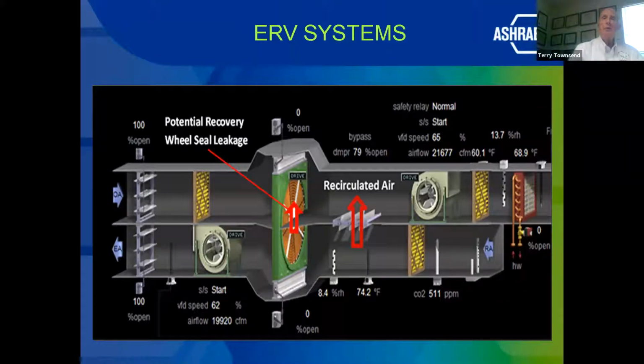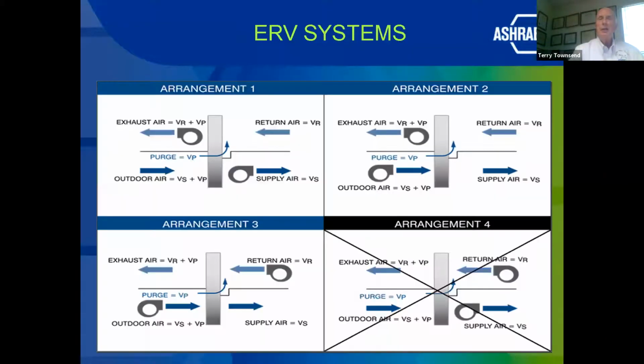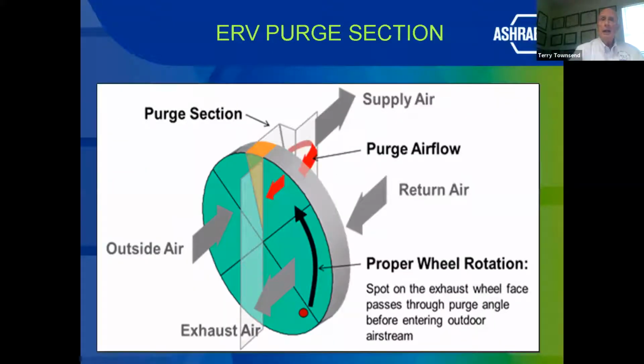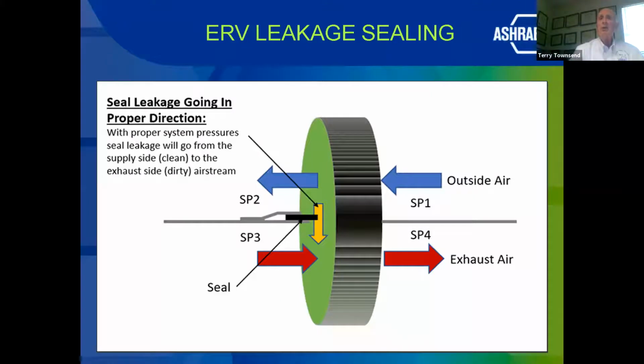Now for energy recovery systems, these next few just show you what a typical system looks like, but then there are concerns. There are 4 different possible arrangements. 3 are recommended because of the bypass air that you might have. The 4th one, you're not bringing in or purging the air properly with arrangement 4. So 1 through 3 is what is recommended. Now, if you want to purge the section, you have to make sure that you have the proper wheel rotation, and then you want to make sure the leakage is going in the proper direction for the outside air as well as the exhaust air.